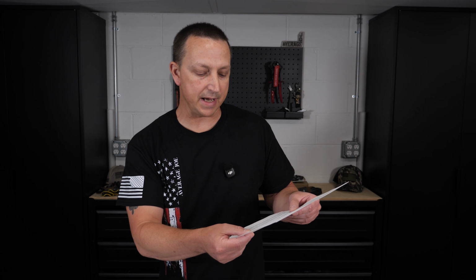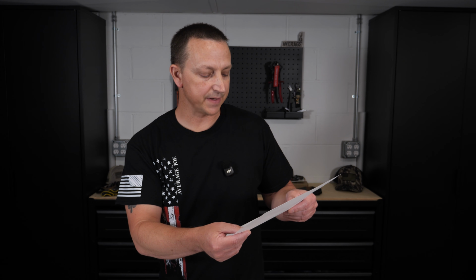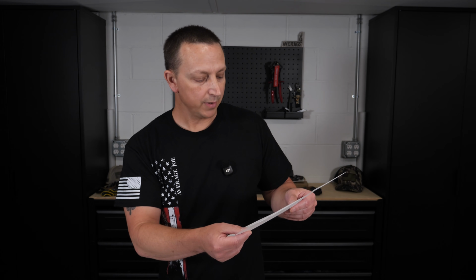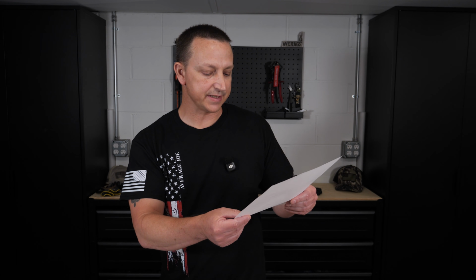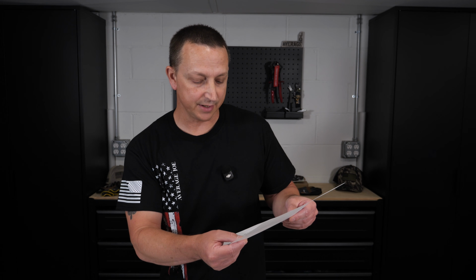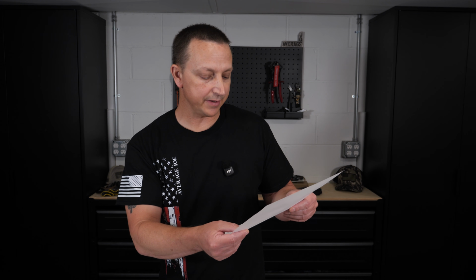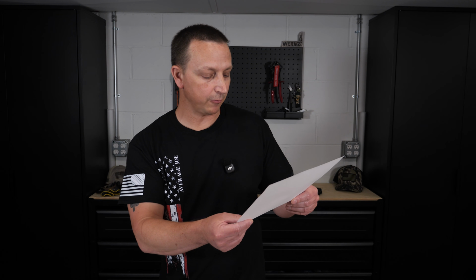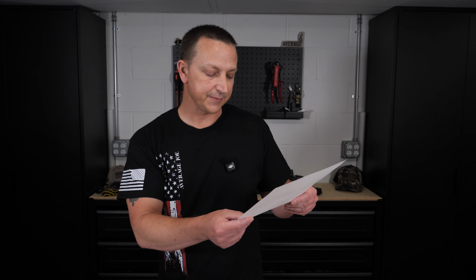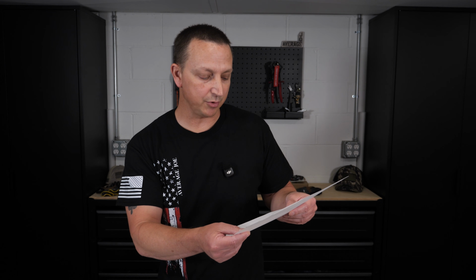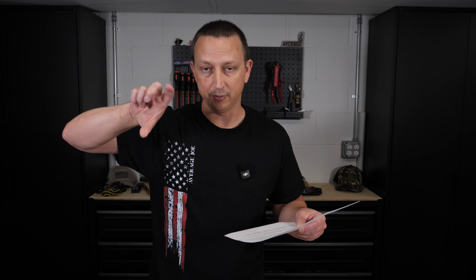After all communication cables are connected, please power on the master battery first, then power on the slave batteries afterward. Once battery communication is successful, the slave batteries should synchronize on/off status with the master battery using the master battery's power button. If synchronization does not work, please power everything down and swap the parallel communication cable positions and then test again. What they're saying there is instead of going from out to in, we'll swap that cable around so it'll be from in to out.